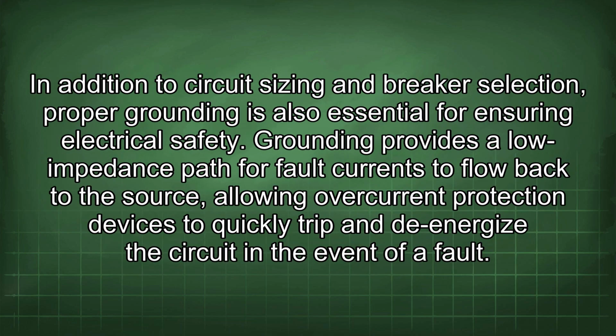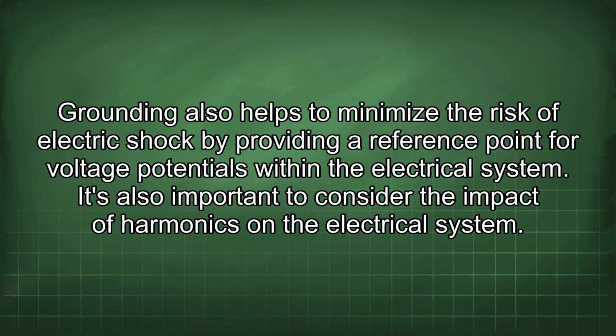In addition to circuit sizing and breaker selection, proper grounding is also essential for ensuring electrical safety. Grounding provides a low impedance path for fault currents to flow back to the source, allowing overcurrent protection devices to quickly trip and de-energize the circuit in the event of a fault. Grounding also helps to minimize the risk of electric shock by providing a reference point for voltage potentials within the electrical system.